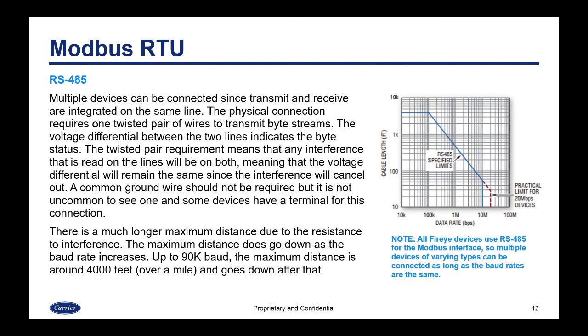There is a much longer maximum distance due to the resistance to interference. The maximum distance does go down as the baud rate increases. Up to 90k baud, the maximum distance is around 4,000 feet — which is just over a mile — and goes down after that.